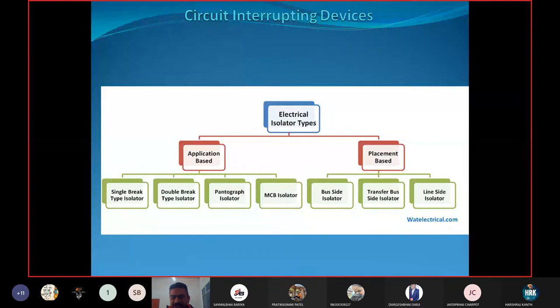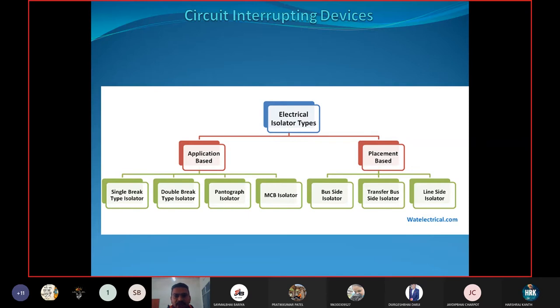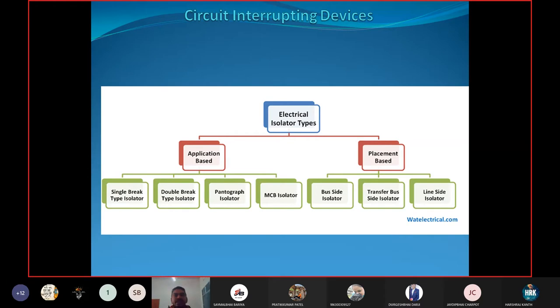An electrical isolator is used in switchyards and substations. The basic function of the isolator is to isolate the system or the line. The isolator is installed with a circuit breaker and is one type of air brake switch. It operates on no-load condition only — we cannot operate the isolator under on-load conditions.